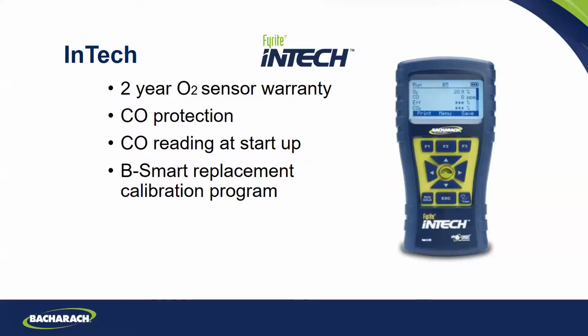and then it will never zero it again. So now it's zeroed in fresh air. And now, if I go into that building where there's 10 ppm and I turn my unit on, it'll say 10. Everyone else will say 0. So it's a great little feature. For those of you that didn't buy the Bacharach, you want to make sure you go outside and turn it on if you think there is CO in that building. If you own this Bacharach and you want to use that feature, you want to re-zero in fresh air about once a month.